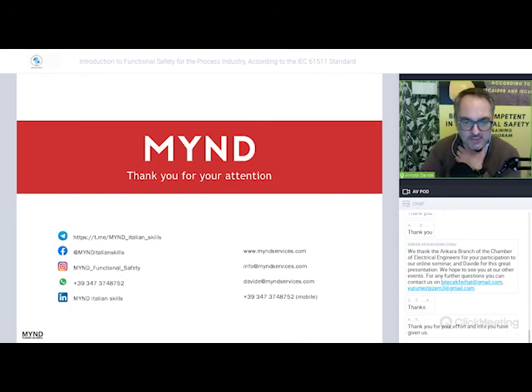Normally, our tendency is to avoid SIL 4 for the process industry, because this means realizing two independent safety instrumented systems. There are no components or devices for the process industry with the SIL capability of SIL 4. To avoid SIL 4, we can apply an additional safety layer independent of the safety instrumented system, and then maybe provide the safety instrumented function by SIL 3. There are a lot of ways to avoid SIL 4, but anyway, SIL 4 is terrible for the process industry.